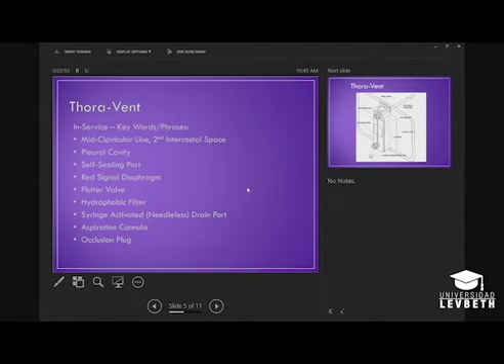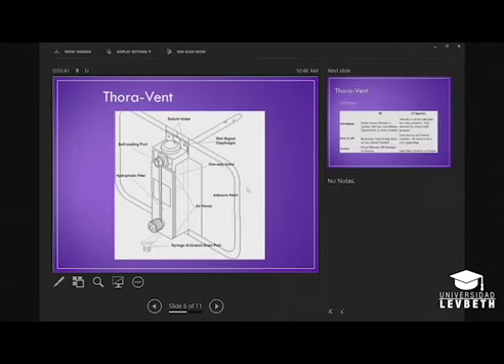The air will rush up the catheter and deflect this red signal diaphragm up and down with each respiration. That gives the doctor visual confirmation that they're in the pleural space. They advance the catheter. There's adhesive sticky backing on the product. They'll stick it up to the chest wall, and it will be working perfectly just like that. But the key for this is it's only for air, no fluid. So if they do have fluid, it's the wrong device. It has a red signal diaphragm that goes up and down. It has a drain port on the bottom that you can aspirate fluid if they do get any unsuspected fluid. And here's a picture of it.